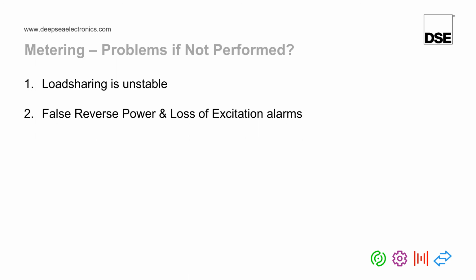Or it could even be that you're requesting the generator to do something and it physically isn't possible. So this might be, for example, asking a 100 kVA generator to produce 200 kVARs. That's far too much for that generator to produce. So when the DeepSea module tries to request the AVR to do that, the AVR physically doesn't have enough power to be able to ask the generator to do that, and therefore gives you AVR trim limits.